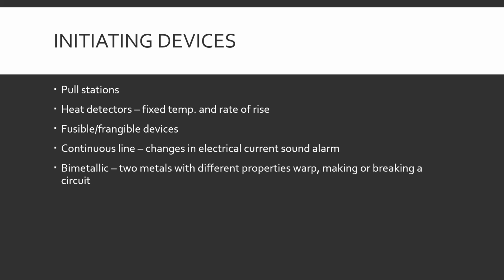And bimetallic. These are 2 metals with different properties that warp, making or breaking a circuit. These are a little more resistant to the problems of a rate of rise, because metal takes time to heat up. They have a certain amount of give, so if someone opens the door and it's warm, the metals may warp, but they won't touch. But if there's a big drastic change in temperature, like 30, 40 degrees, one metal will expand quicker than the other. They'll touch or break contact. That changes the voltage in the circuit, or closes the circuit or opens it, and that sets off the alarm.